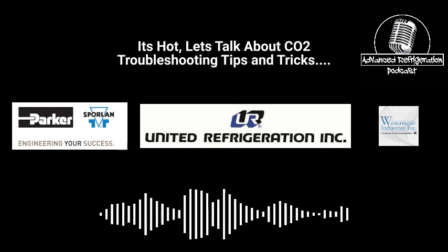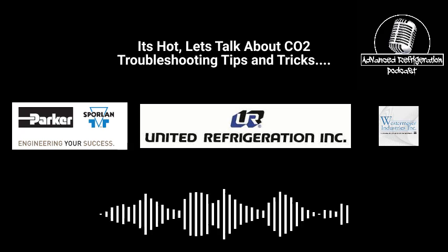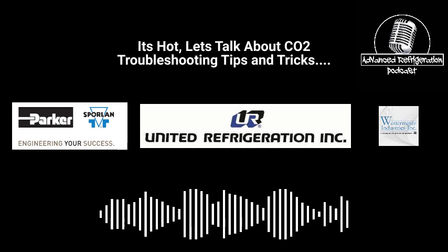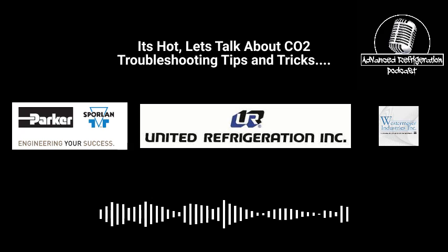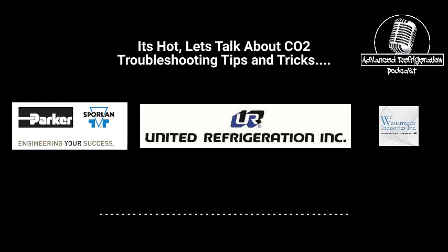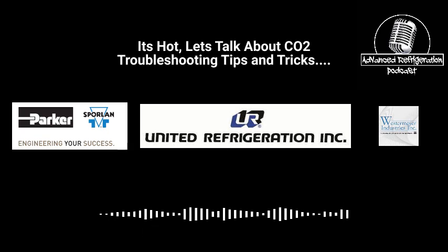Now, if you use, like Kaiser was using DC solenoids, yeah, they were wearing out after a thousand or so cycles. That's 146,000 cycles a year if you did the 400 cycles a day. Yeah, so I bet that oil solenoid is cycling that much. But what Kaiser was doing is they were using a DC solenoid coil. CPC contacts are not DC rated. Correct. The coil is, but the actual contacts are not DC rated. So it actually derates the contacts, so they were failing after a couple thousand cycles.